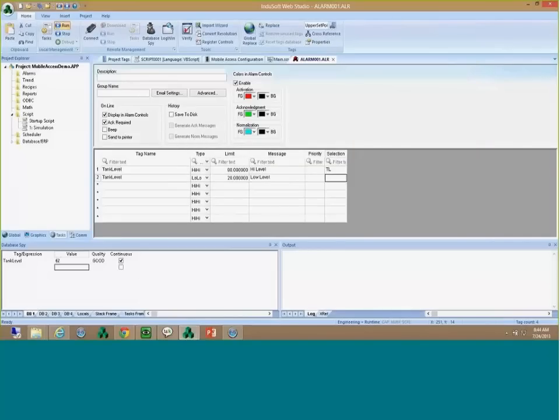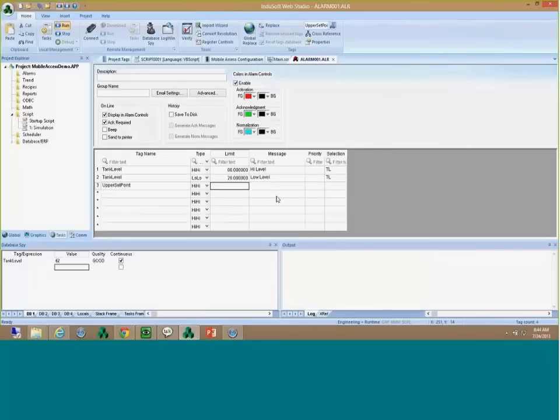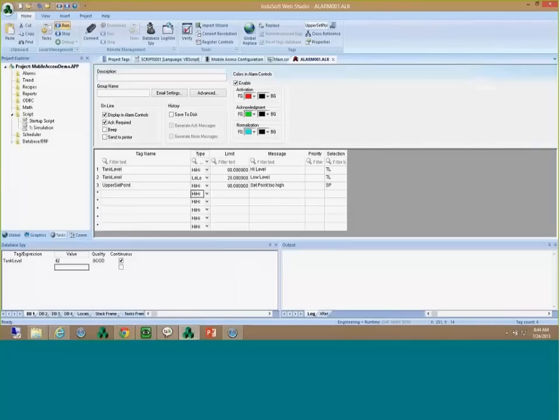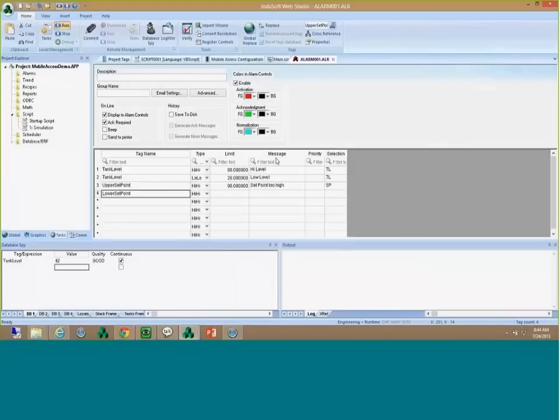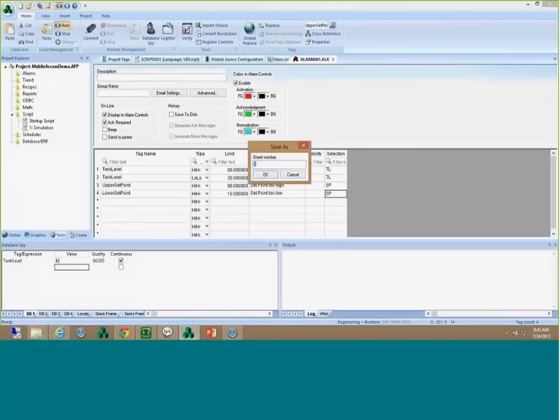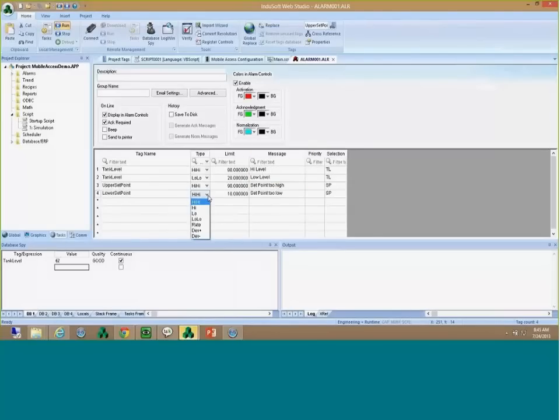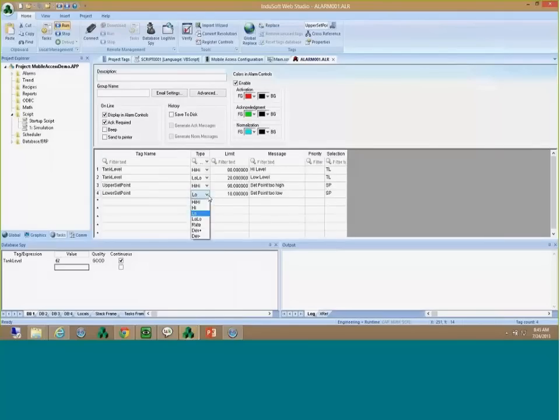I also want to warn the user if their entered set points are out of reasonable limits. I'll configure the upper set points — if above 90, show 'set points too high' with selection 'SP'. And something similar for lower set points — if below 10, show 'set points too low' with selection 'SP'. I'll save this alarm worksheet. Now I have alarms configured, and if I look at the iPod, I already see an alarm saying the set point is too low.